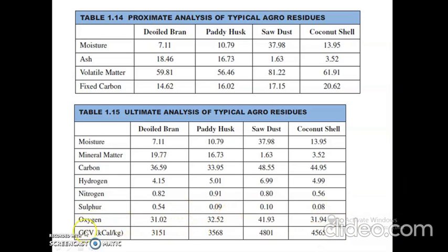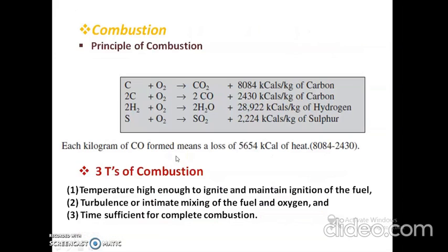So while selecting your biomass for the boiler, you must also check the gross calorific value, and you have to compare it with the conventional fossil fuels. Suppose for solids you are replacing coal with agro residue or biomass, you must compare them with respect to proximate and ultimate analysis.